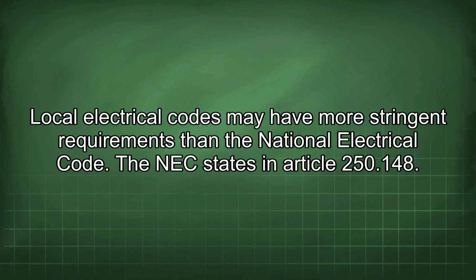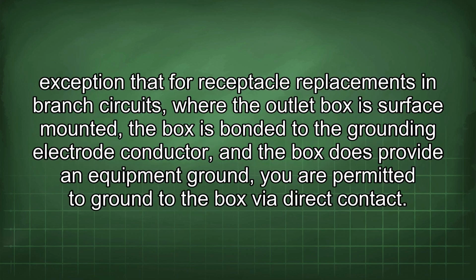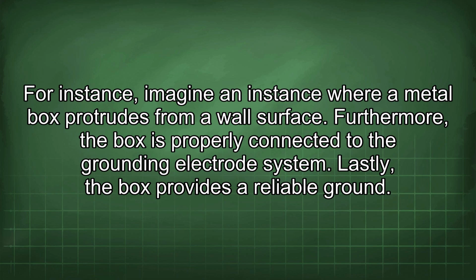The NEC states in Article 250.148, exception, that for receptacle replacements in branch circuits, where the outlet box is surface mounted, the box is bonded to the grounding electrode conductor, and the box does provide an equipment ground, you are permitted to ground to the box via direct contact. For instance, imagine an instance where a metal box protrudes from a wall surface. Furthermore, the box is properly connected to the grounding electrode system. Lastly, the box provides a reliable ground.